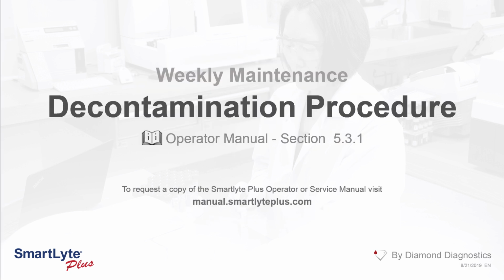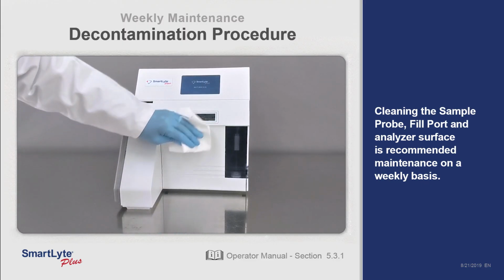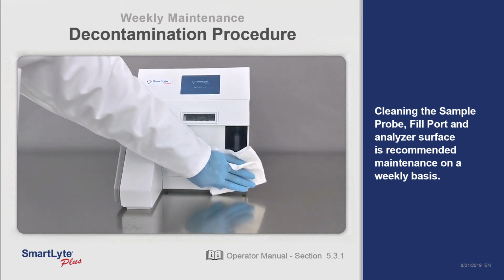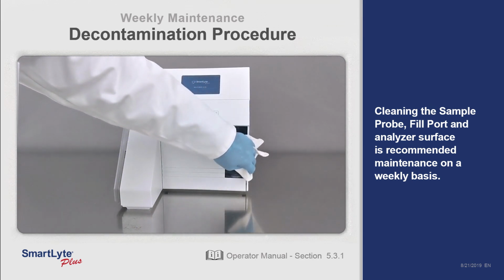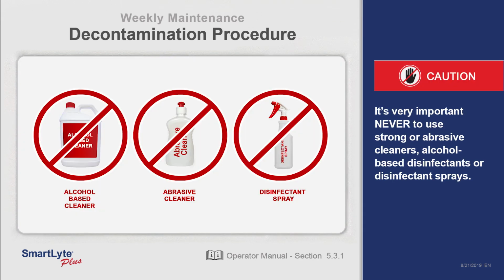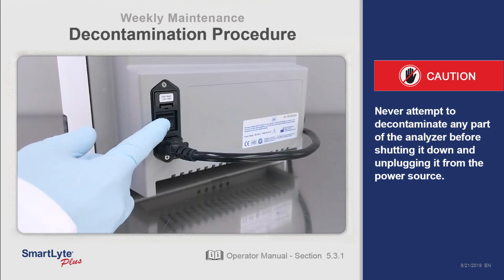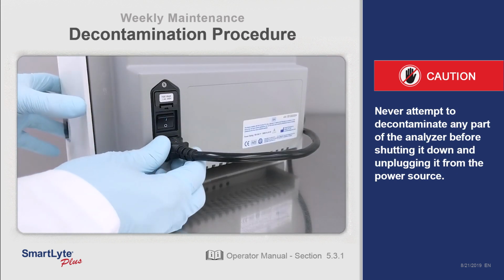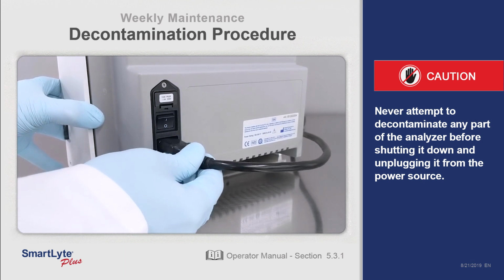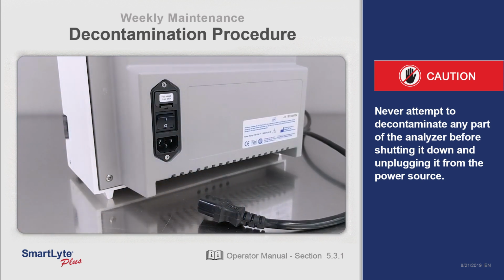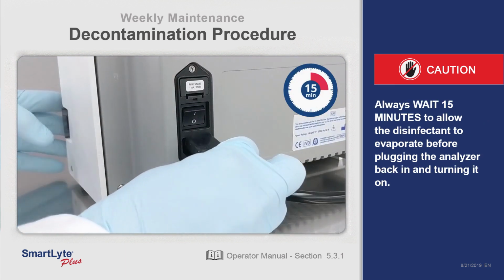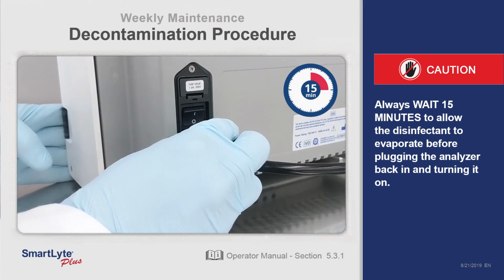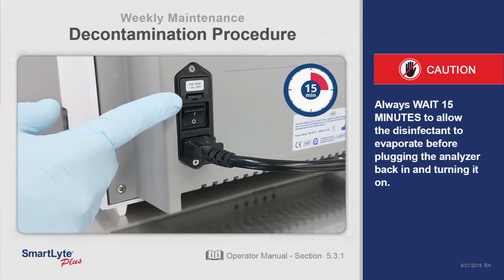Decontamination procedure. Cleaning the sample probe, fill port, and analyzer surface is recommended maintenance on a weekly basis. It's very important never to use strong or abrasive cleaners, alcohol-based disinfectants, or disinfectant sprays. Never attempt to decontaminate any part of the analyzer before shutting it down and unplugging it from the power source. Always wait 15 minutes to allow the disinfectant to evaporate before plugging the analyzer back in and turning it on.